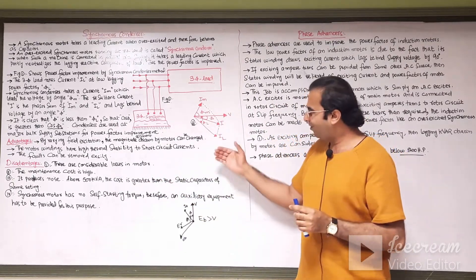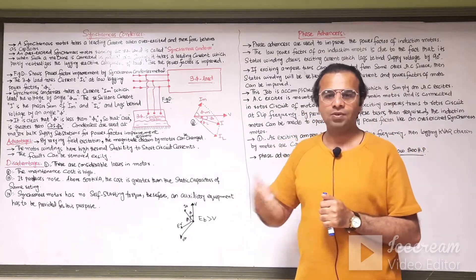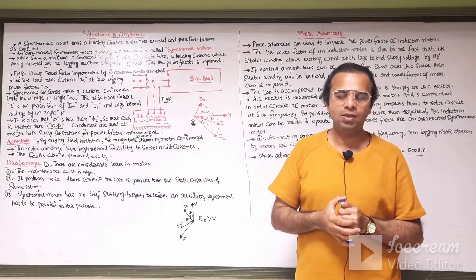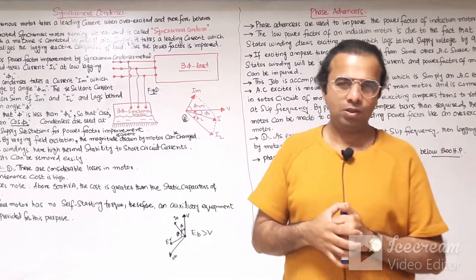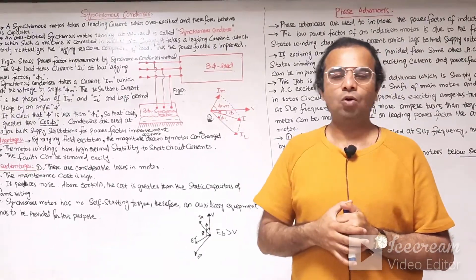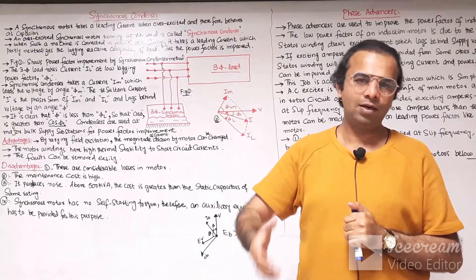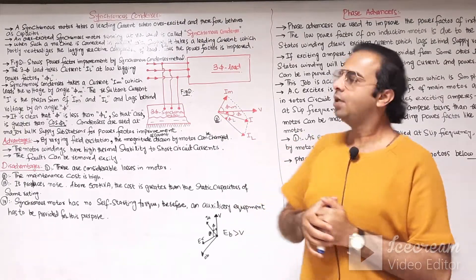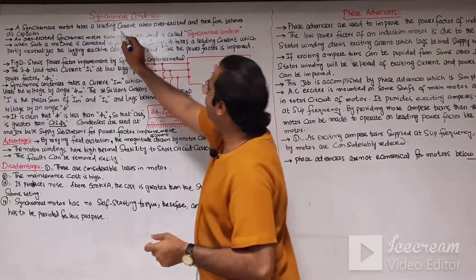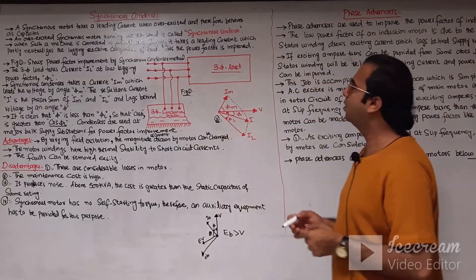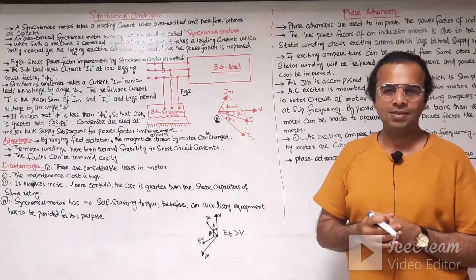The first improvement technique we are going to discuss is the synchronous condenser. When a synchronous motor is running at no load under over-excitation conditions, it takes a leading current from the main supply. A synchronous motor takes a leading current whenever over-excited, and therefore it behaves as a synchronous capacitor.